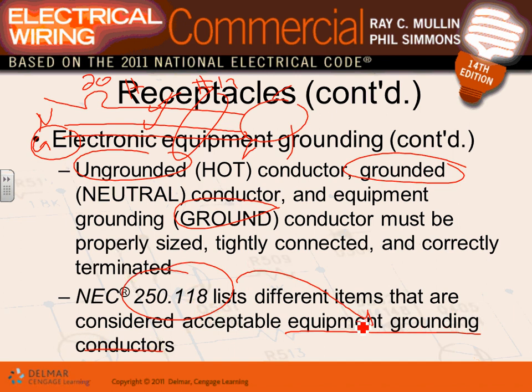Number one, you either have a conductor. Number two, do you see the EMT conduit right there? The conduit itself acts as an equipment grounding conductor. A different type of conduit, all metallic conduits, non-flexible metallic conduits act as an equipment ground conductor. So inside that conduit, do you need an equipment ground conductor? No. Do some people put an equipment ground conductor in it? Yes, especially if it's an isolated, insulated equipment ground conductor.